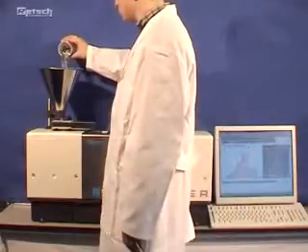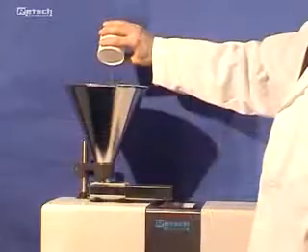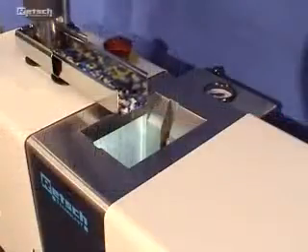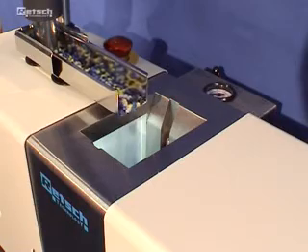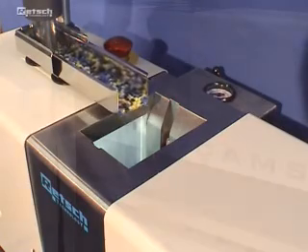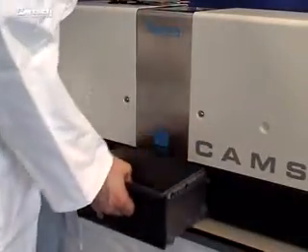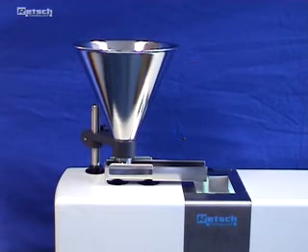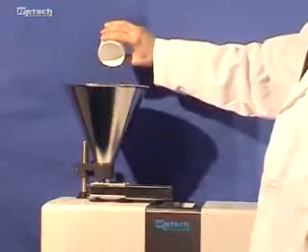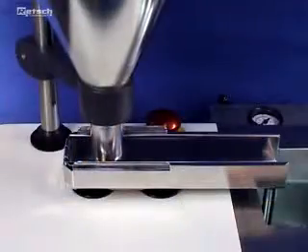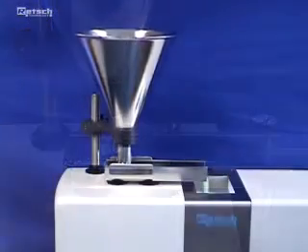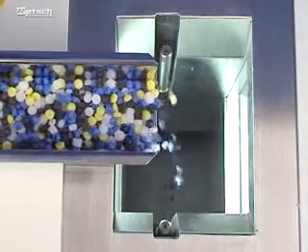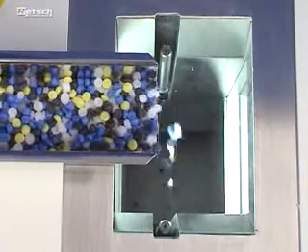The appliance of the Camsizer is very convenient to the user. Optical measurement without physical contact takes place as the sample falls from the hopper and vibrating channel past the screen into the collecting vessel. To avoid dust expansion, the hopper is lowered to the feeder via software control. The sample is filled into the hopper and the implemented auto height unit raises the funnel to its pre-chosen position. The feeder is also software controlled and ensures a permanent flow of material.